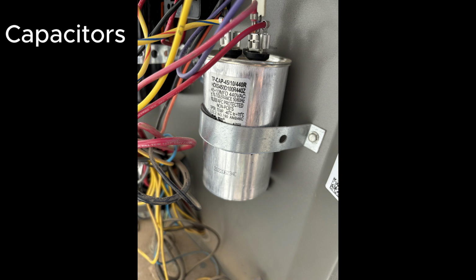So just be aware that they are a thing, a very common repair that we make as technicians, and they need to be replaced maybe 2 to 3 times throughout the lifespan of a unit. They often lose their charge more quickly if it's extremely hot, or if there's a lot of over voltage, which can happen from the electrical company. You can get a surge protector to address that.